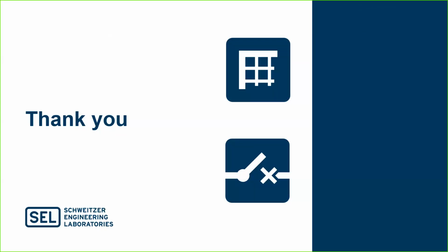But usually, if you have a voltage concern, you want your FLISR system to not restore if the voltage is going to be unacceptably low. As of right now, FLISR does not look at voltage at all. What we're looking at is, should it just not restore if the voltage will be unacceptably low, or do we need to add an integration mechanism whereby it can ask for the voltage to be raised, or it can disable a CVR scheme and wait until it gets a signal from that scheme saying, yeah, it's off, we're good, and then it can proceed. That's what we're looking at right now. So FLISR today is not looking at voltages at all, but in the near future it will.